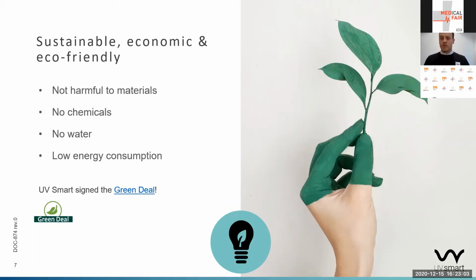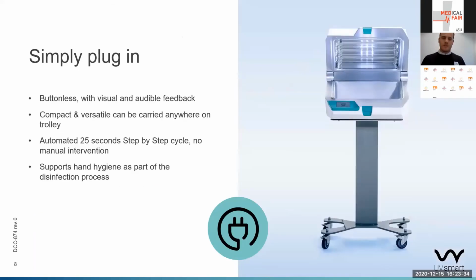Also, because we don't use chemicals, there's no water. We call it a cold and dry disinfection because the chamber does not heat up and no liquid is used. This means you can easily put in electronic devices, and it has very low energy consumption. The device roughly takes 150 watts per 25 seconds, about as much as a laptop. So there's no big impact on the environment or on the installation.